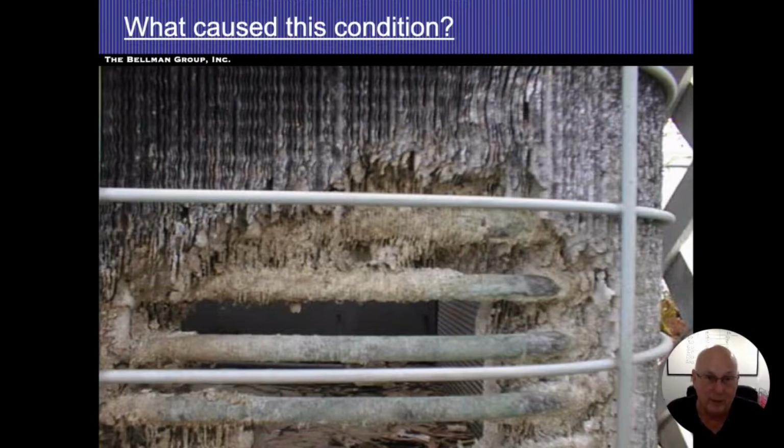Those fins are very thin and they're fragile. All right. So a dog's urine sometimes is pretty acidic. So if they keep peeing on the air conditioner all the time, then it wears away at the fins. Now, it didn't hit the copper tubing. It didn't damage that. But the fins that are on there, that it did damage.